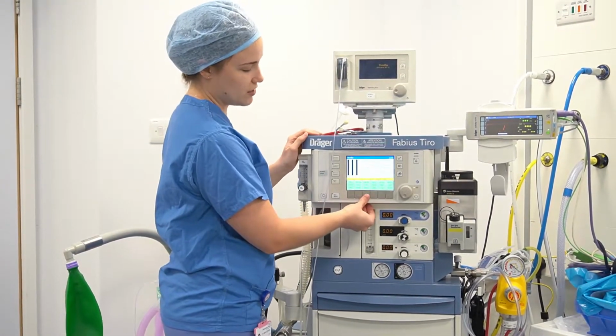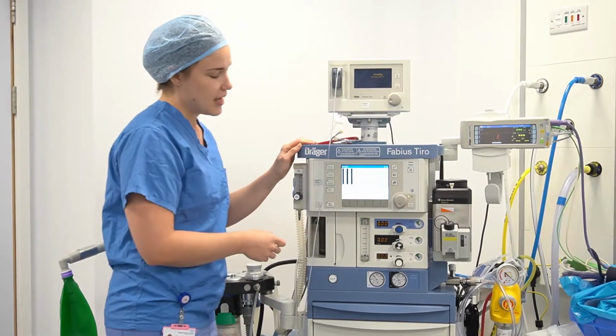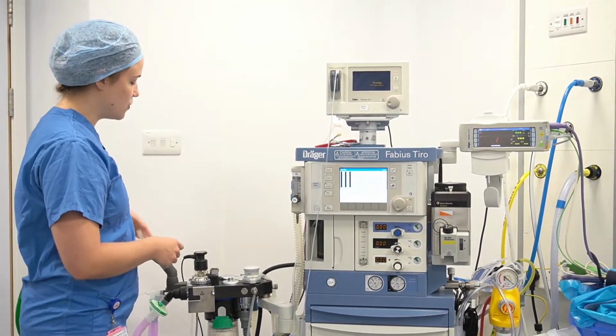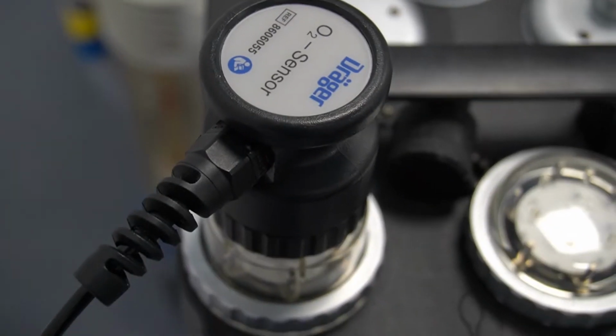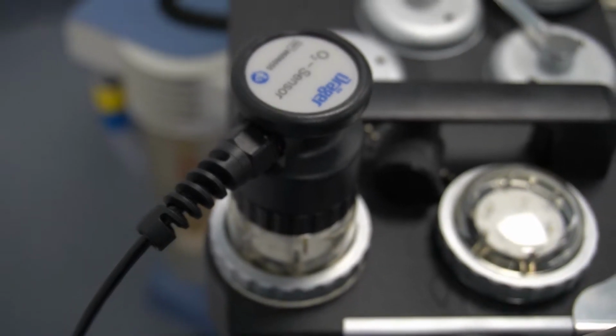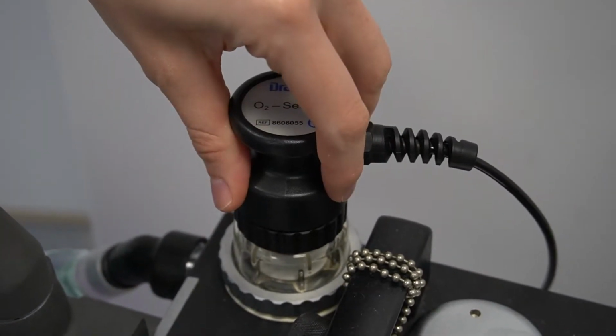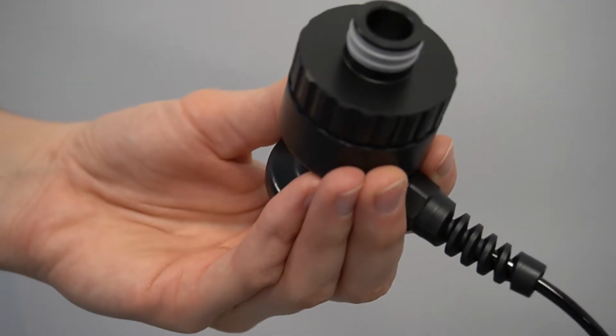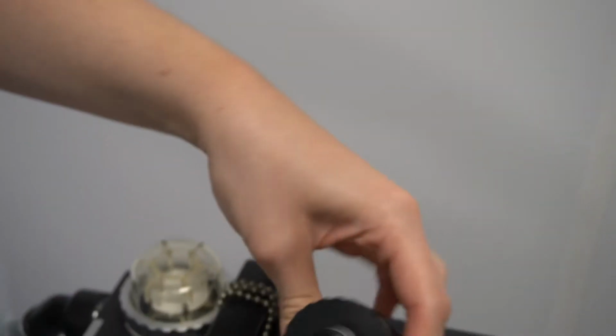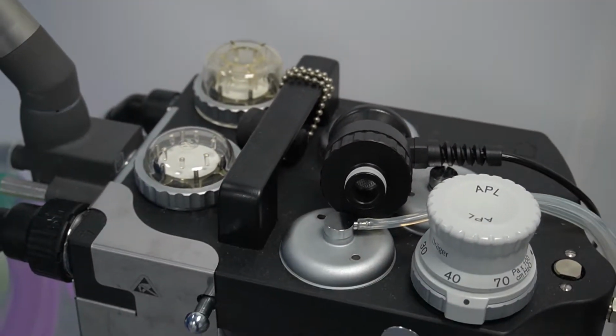to calibrate the O2 sensor. So again, pushing it there. Then looking at your O2 sensor, they're going to tell you to remove it and to expose it to room air for 2 minutes. So that's done by literally just lifting it off, and you can just put it down there and expose it to room air for 2 minutes.